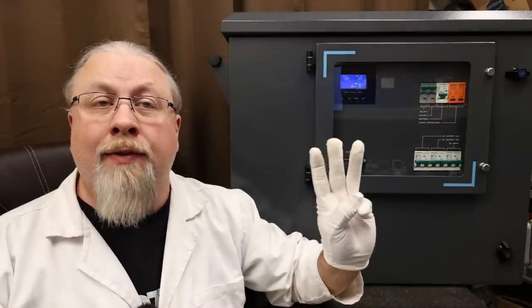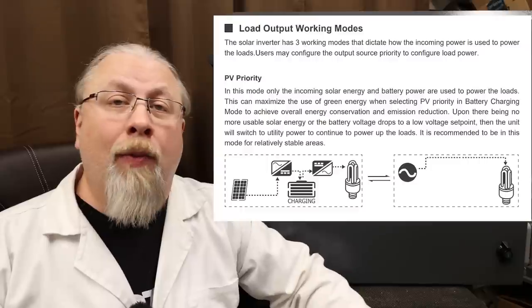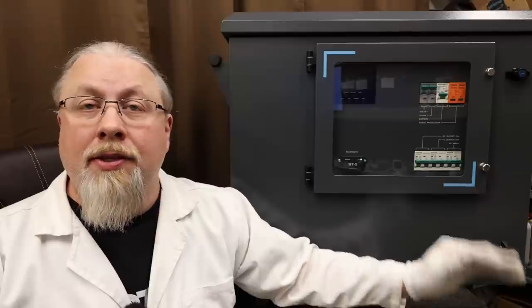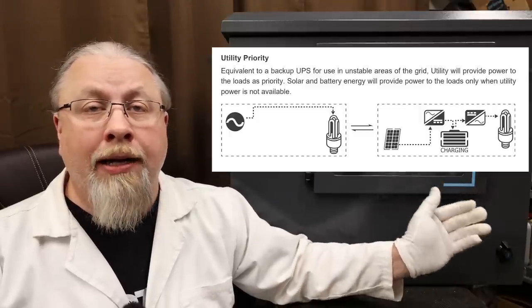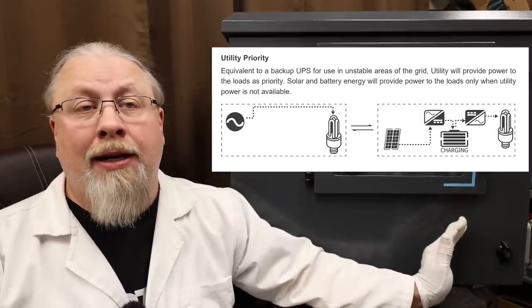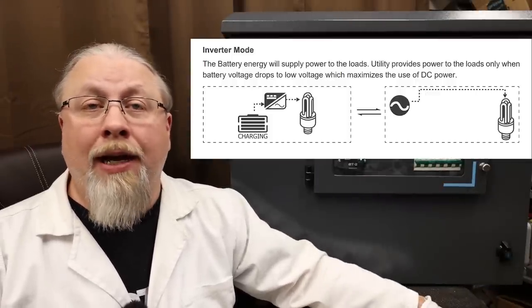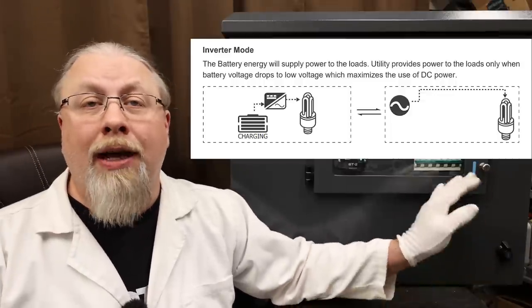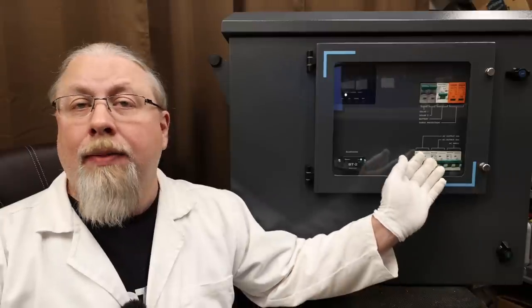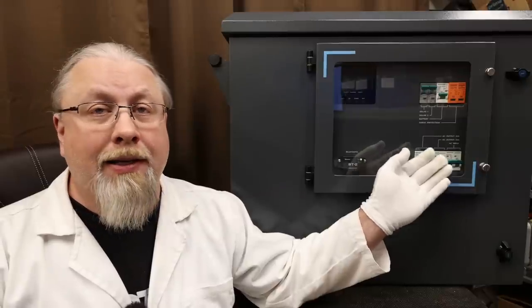The inverter does offer three modes of operation. One is called PV priority, which will use solar plus battery to power the loads. Once the battery drops low enough, then AC power will pass through. Utility priority mode acts like a standard UPS. It will use AC to power the loads at all times unless the AC power gets shut off. Then there's raw inverter mode and that will power the inverter only with the battery until the battery drops to such a low level that AC power will then pass through. That latter mode would be useful for charging up the battery during the day with solar and then using the battery at night to power the loads, basically to save you on electricity.